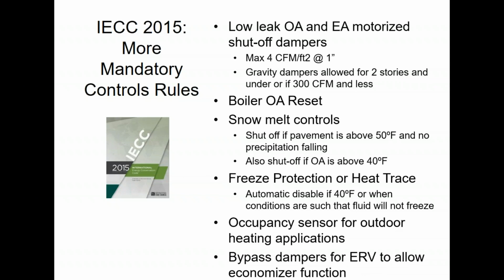For ERVs, if you have an ERV system, which is sometimes required by code, but even if you put an ERV in, not required by code, you just want to put one in, that's fine. But as soon as you put an ERV in, you have to have bypass dampers on the ERV. And those bypass dampers act like an economizer. You use the typical economizer settings, if you will, the 70 degrees, the enthalpy setting, all that kind of stuff, to determine if free cooling is available. And if it is, you shut off your ERV.